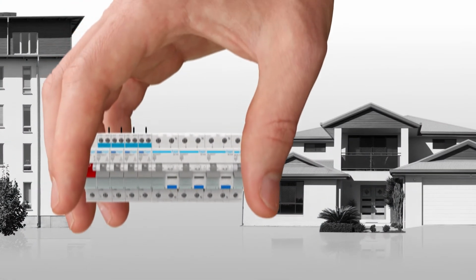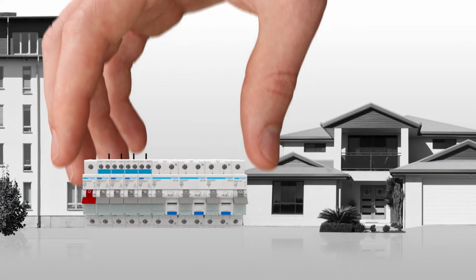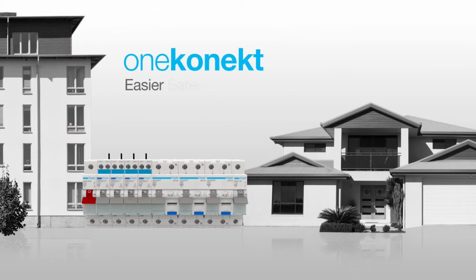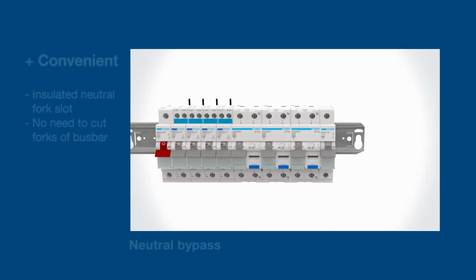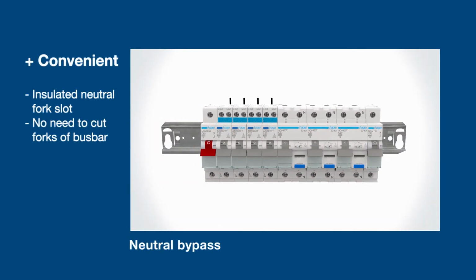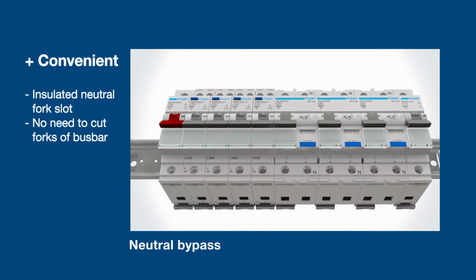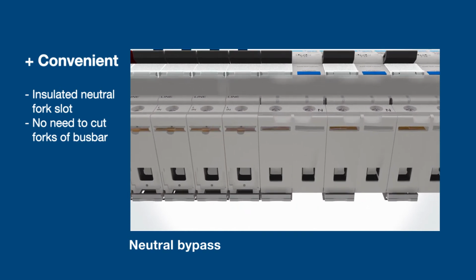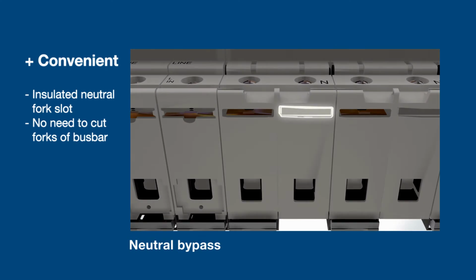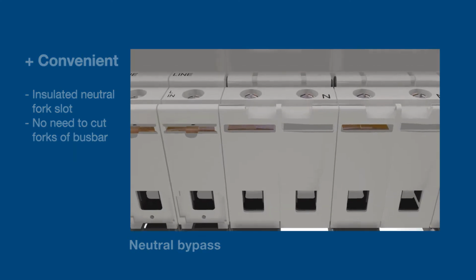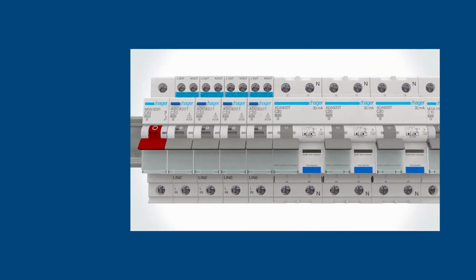The Onekonekt system from Hager is the new benchmark in residential protection, with many new unique features to make installations easier, safer and faster. One key feature of the Onekonekt system is the insulated neutral fork terminal in all of our two-pole devices, allowing a single busbar across all devices without the need to cut any busbar forks.